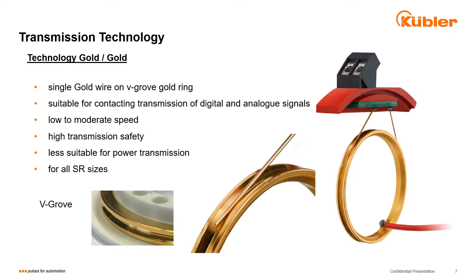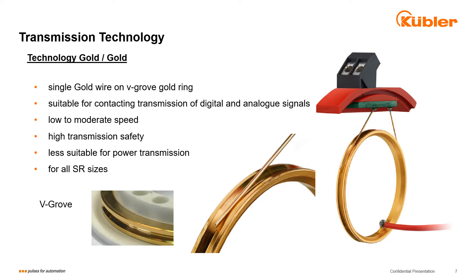Gold coatings are widely used in static connection technology. With slip rings, this type of electroplating is only one method of ensuring reliable signal transmission. It is usually a gold-plated spring-type wire or a pure gold wire that runs on a gold-plated ring with a V-guide groove. This technology is suitable for low-speed applications and offers the possibility for a quite narrow axial arrangement, leading to shorter slip rings. The electrical values of gold-gold are on a similar level to those of silver technology.